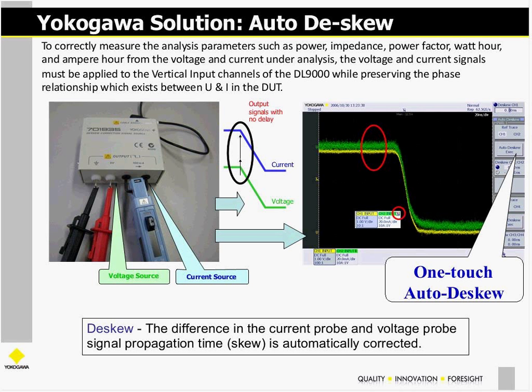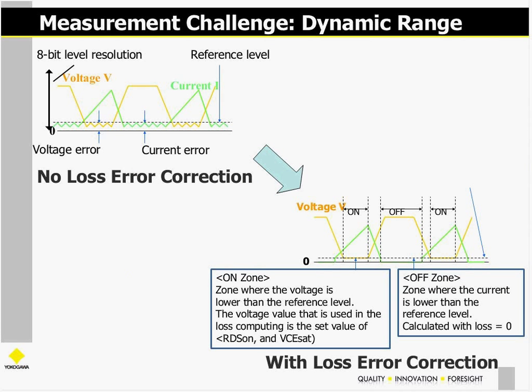Here are a couple of photographs. If you own a Yokogawa scope and an auto Deskew box, this is how you connect your probe. The current probe here is a Yokogawa probe, and then the differential probe here—you can do this with a single-ended probe as well. Then you hit Deskew, and it will align the two waveforms. You'll definitely see the difference in your measurements, and you'll also see the difference in the waveforms on the screen.